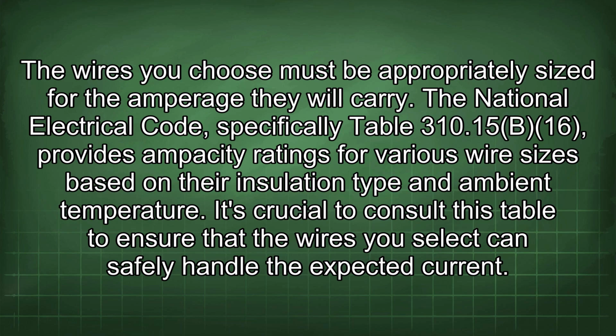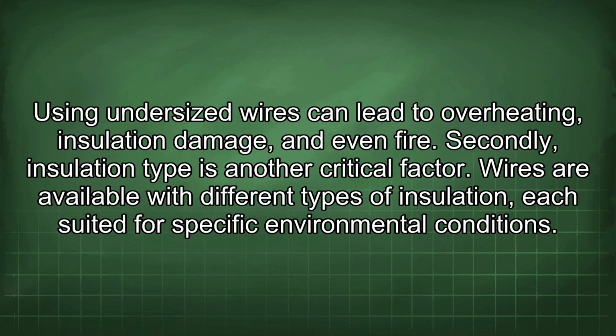The National Electrical Code, specifically Table 310.15(B)(16), provides ampacity ratings for various wire sizes based on their insulation type and ambient temperature. It's crucial to consult this table to ensure that the wires you select can safely handle the expected current. Using undersized wires can lead to overheating, insulation damage, and even fire.